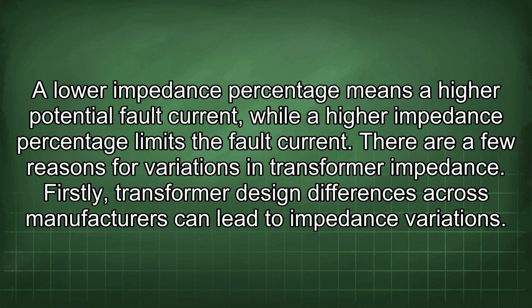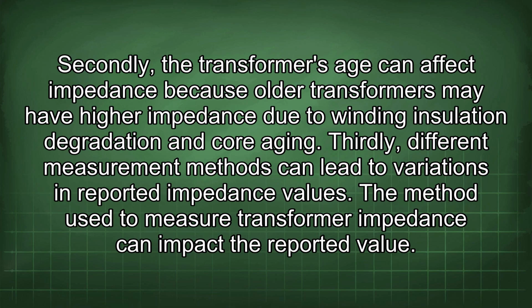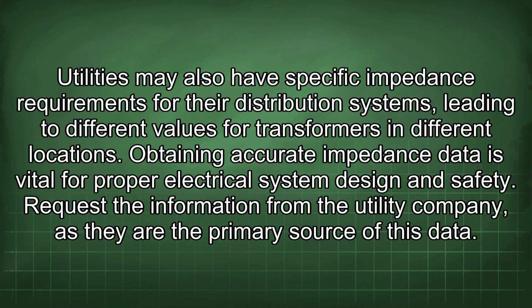There are a few reasons for variations in transformer impedance. Firstly, transformer design differences across manufacturers can lead to impedance variations. Secondly, the transformer's age can affect impedance because older transformers may have higher impedance due to winding insulation degradation and core aging. Thirdly, different measurement methods can lead to variations in reported impedance values. The method used to measure transformer impedance can impact the reported value. Utilities may also have specific impedance requirements for their distribution systems, leading to different values for transformers in different locations.